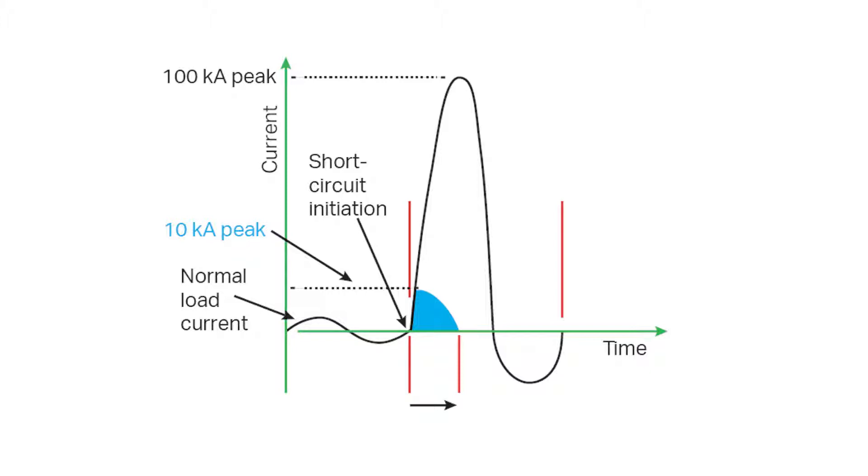In the first major fault current cycle, depicted by the waveform, a non-current limiting overcurrent protective device would let through approximately 100 times as much destructive energy as a current limiting fuse. This is assuming an asymmetrical peak current of 100,000 amps and a peak let-through current of 10,000 amps.